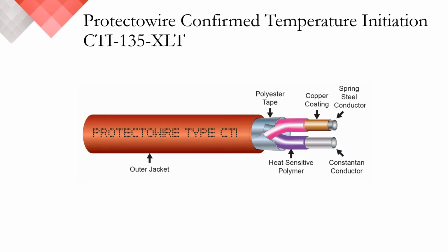Featured in this slide is our CTI 135 XLT. CTI stands for, as we mentioned earlier, the Confirmed Temperature Initiation Technology. Please note that unlike the PHSC 135 XLT, which uses two of the same spring steel metal conductors, the two metal conductors in this image are dissimilar metals. The metals shown here actually form a T-type thermocouple, allowing us to determine the temperature at any shorted point on the detector. This technology does require the use of a universally compatible CTM series interface module. This module provides the interface between our CTI series detector and a standard IDC or addressable module.